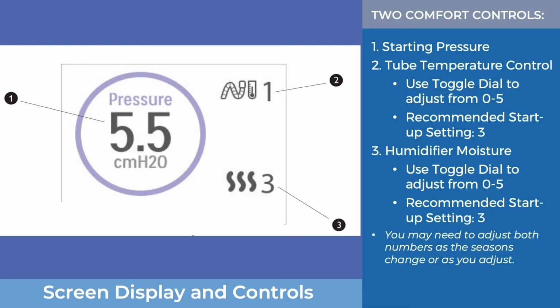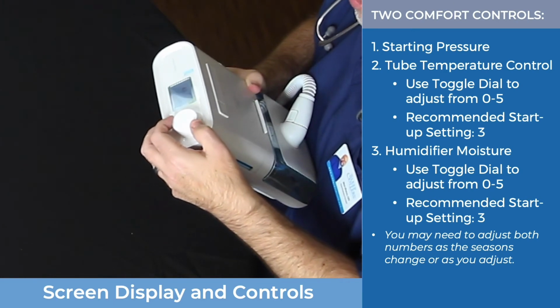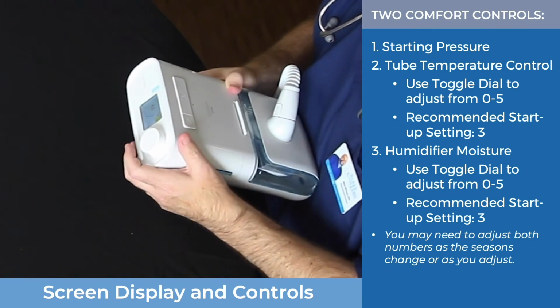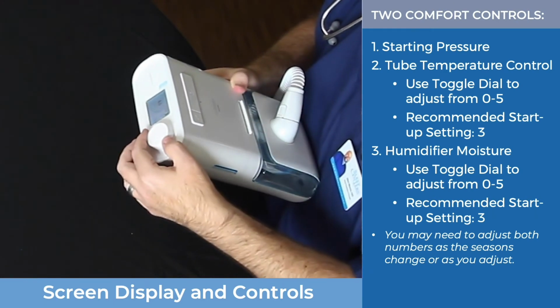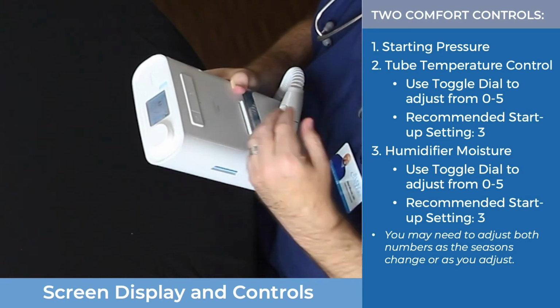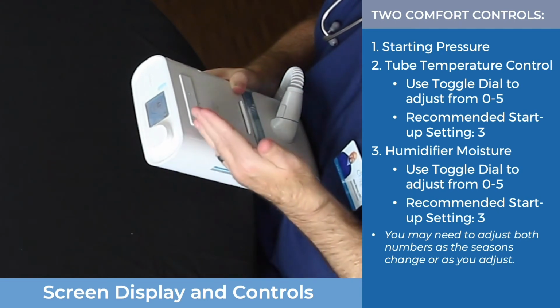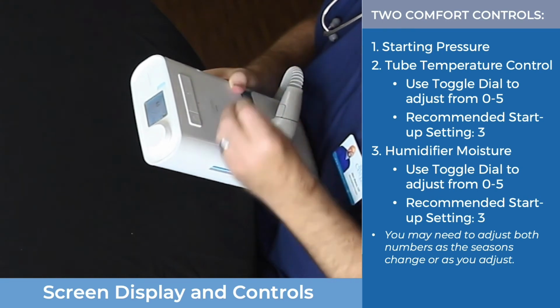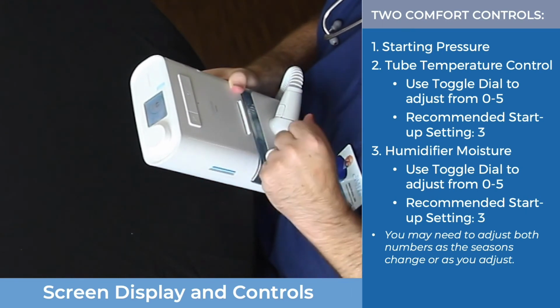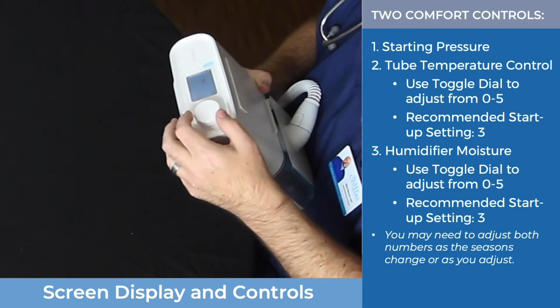And then you have these two numbers to the right side, which are humidity and temperature control. So the top number here is your tube temperature control. You actually get to control the temperature of the air coming out of the tube. And if you want to adjust that, you toggle with the dial until you highlight that number. You click the button, and then you can turn to adjust. Higher the number means warmer air. Lower is cooler. Your range is 0 to 5. We recommend that you start at 3 and then adjust as you're comfortable.